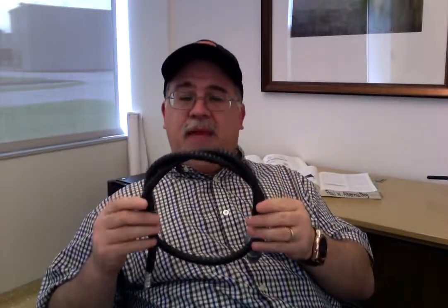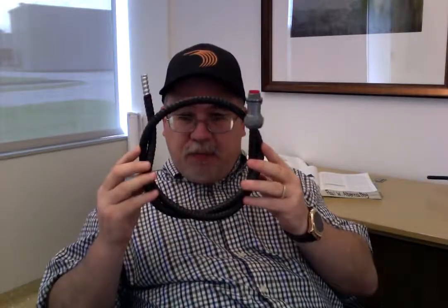All right, now let's talk about a wet location. In a wet location, in order to use a type MC cable in that application, and in accordance with 330.12, which says that if you have a product and you install it in a certain environment, then it has to be rated for that environment. Well, there you go. So now I have a PVC jacketed MC product.